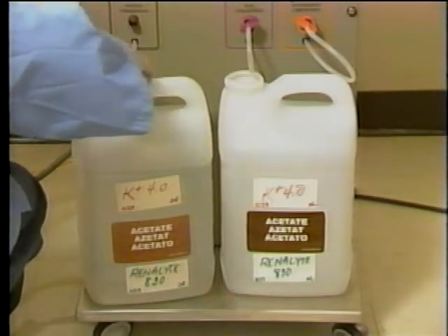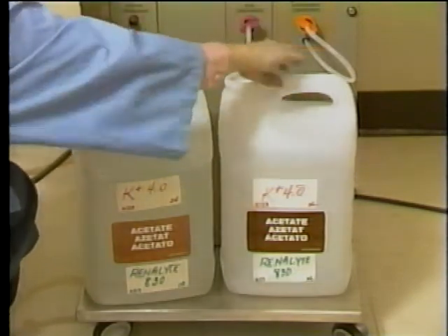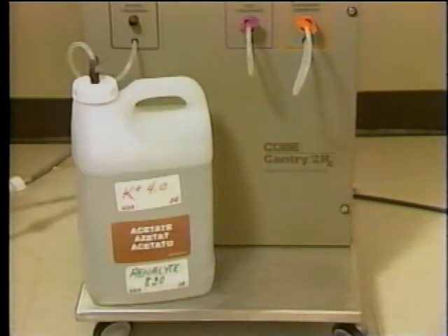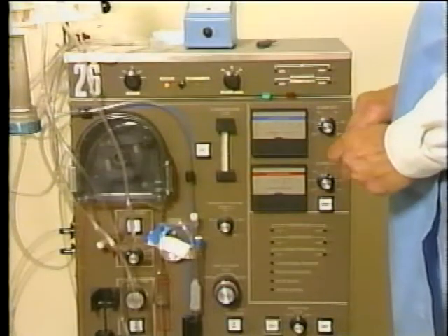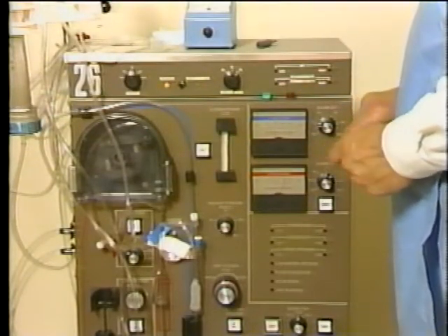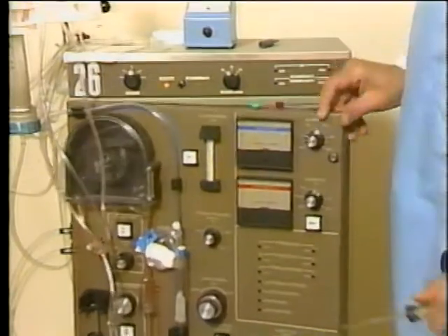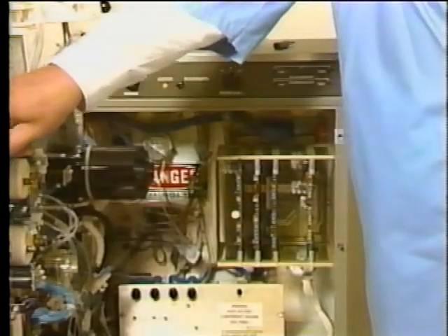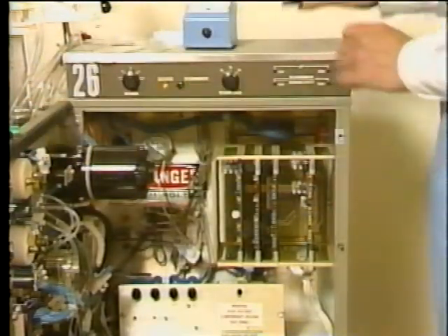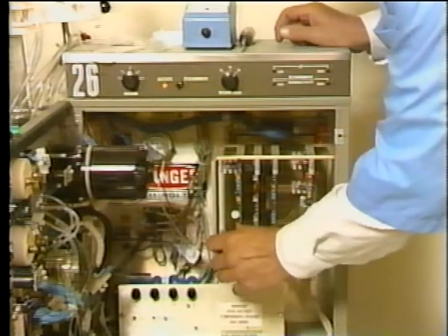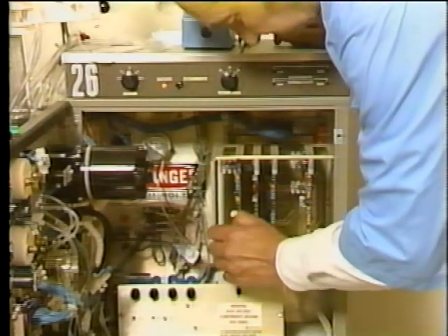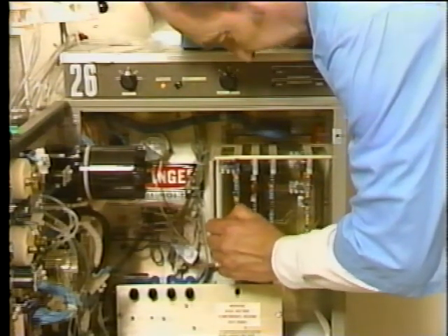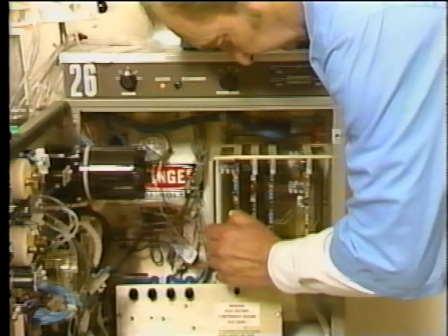These events by themselves do not usually cause serious problems. However, if they occur when the conductivity meter has been miscalibrated or the conductivity alarm limits indiscriminately altered, the outcome for the patient may be serious injury or death. Any calibration or servicing is a maintenance function and should not be conducted while patients are being dialyzed.